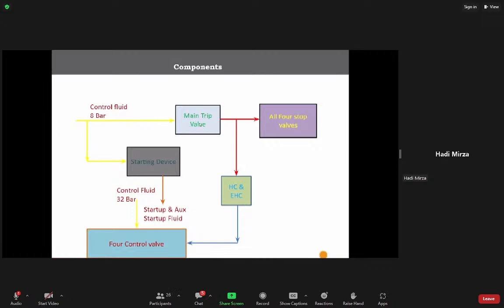Control oil comes to the main trip valve and then four stop valves, and this trip oil is coming to hydraulic and electro-hydraulic devices, and then it goes as a secondary oil to four control valves, whereas 8 bar is coming to the starting device for resetting these valves, and then it becomes auxiliary startup and startup fluid. Whereas this control fluid is 32 bar, the servo motor will work on this 32 kg control fluid pressure.